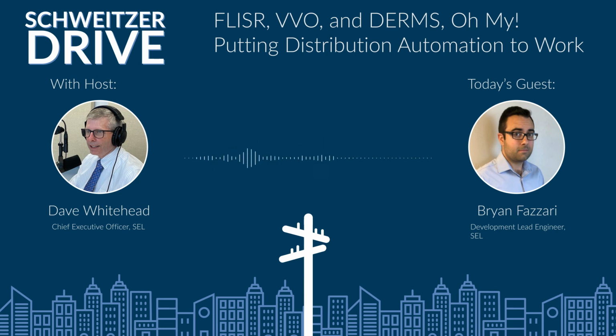So utilities are increasing their number of reclosers. The number going out onto the line is getting higher every day. We have customers telling us: if I have 2 miles of conductor, I need reclosers bounding that area; if I have a couple hundred, maybe 400 customers, I need reclosers bounding that area; if I have a certain number of megawatts per zone, I need reclosers bounding that area. They're trying to figure out how to sectionalize and react to a problem quickly and with great precision. So they're adding places where we can automatically break the line with a switch or recloser all over the place.